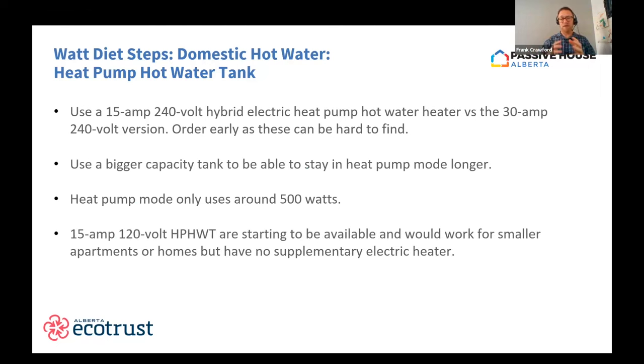And there's also some smaller 15 amp 120 volt heat pump hot water tanks that are coming out. They're available in the States. I'm not sure if they're totally available in Canada yet, but probably will be in a year or two. They don't have the electric resistance backup. So they might be good for smaller apartments or smaller homes that don't need a whole lot of hot water back to back to back.